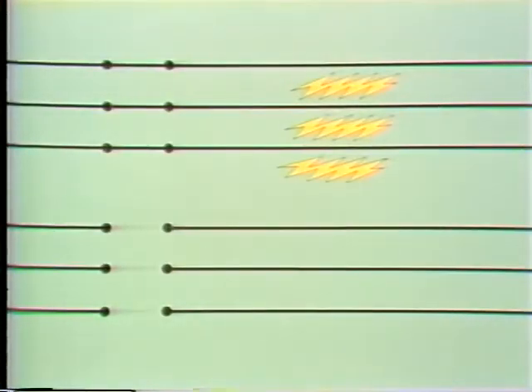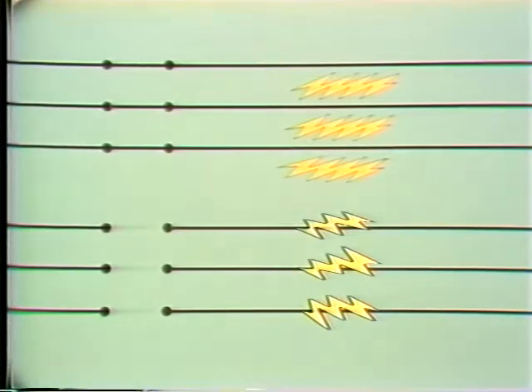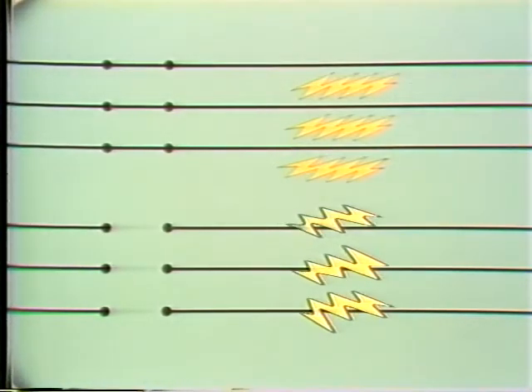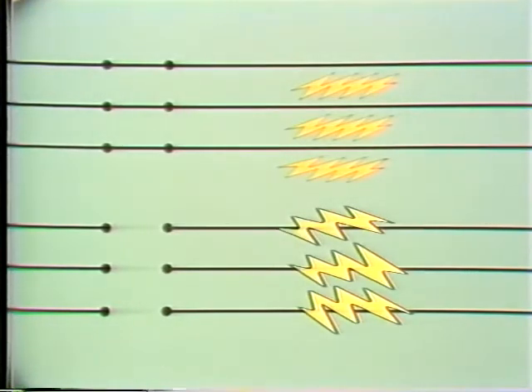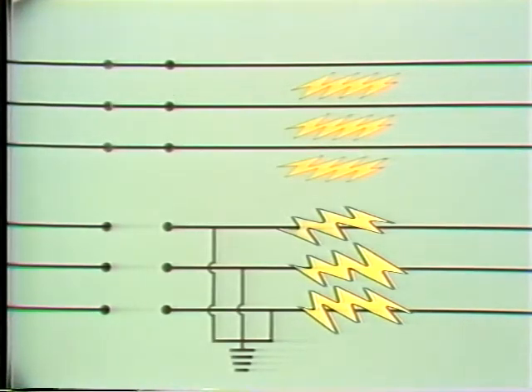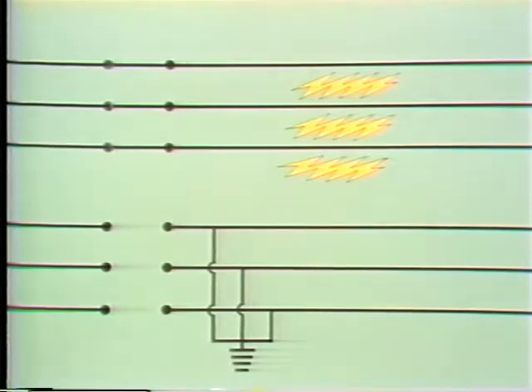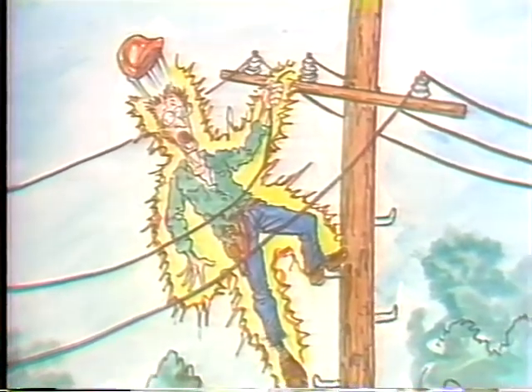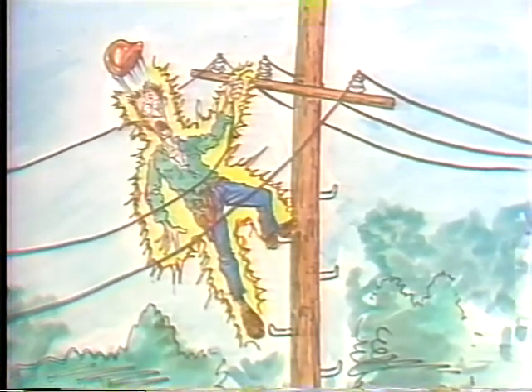Here's an example. Two high voltage transmission lines run side by side. One's energized and one isn't. The energized line is surrounded by an electrical field, and since the field intercepts the de-energized line, it induces a voltage there. Due to capacitive effects, the charge continues to build up. The voltage in the de-energized line can be as high as that in the energized line nearby. To make the de-energized line safe to work on, the induced charge has to be drained off by grounding the line. The grounds discharge the induced voltage into the earth. If a line's not grounded properly, it can store up thousands of volts, even if it's not connected to any power source.